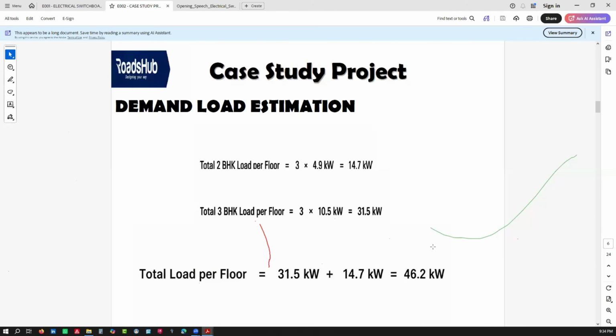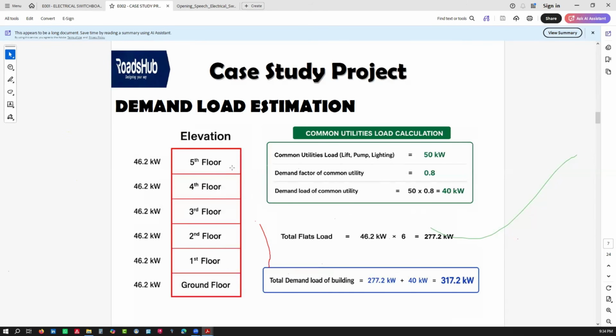But now, let me tell you, people have different design processes based on standards. I've actually seen standards that do values based on kVA per square meter, and that is a specific standard that they use. So if you know your building, you can come up with an estimate table and design for specific loads. But in our country, which is Kenya, we do what we call load analysis. We do load analysis, get the total loads, then get your demand load, and then add them. So once I add, I get 46.2 as the amount of power each floor is required to have.